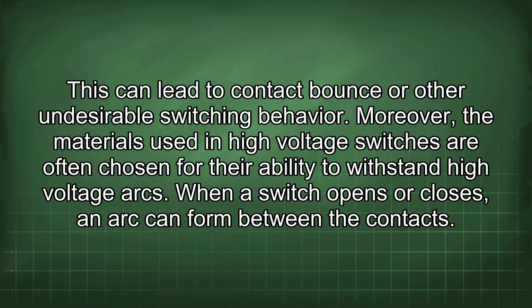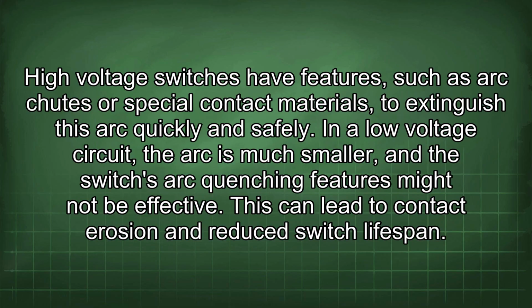Moreover, the materials used in high voltage switches are often chosen for their ability to withstand high voltage arcs. When a switch opens or closes, an arc can form between the contacts. High voltage switches have features, such as arc chutes or special contact materials, to extinguish this arc quickly and safely. In a low voltage circuit, the arc is much smaller, and the switch's arc quenching features might not be effective. This can lead to contact erosion and reduced switch lifespan.